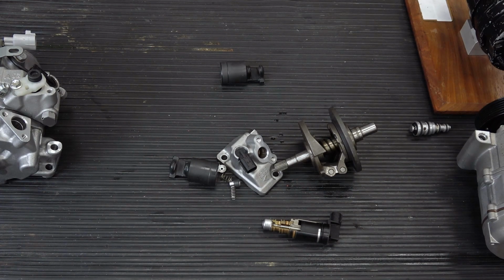And so oftentimes, when I drain old compressors, or even if you look at the waste oil bottle on the side of your recovery machine, you've got this fine microscopic abrasive particulate that is literally distributed throughout the entire system after a catastrophic compressor failure. Therefore, if you're replacing your compressor and you want a comeback-free, ice cold air repair, you need to understand that every inch of the refrigerant path should be either new or flushed, one or the other. So the question I'm often asked is: hoses and lines, should I flush them or replace them?